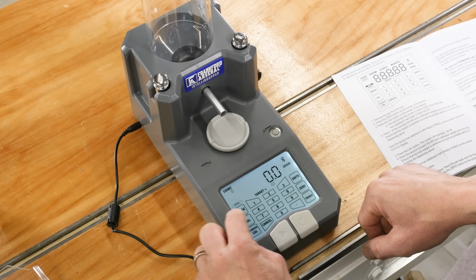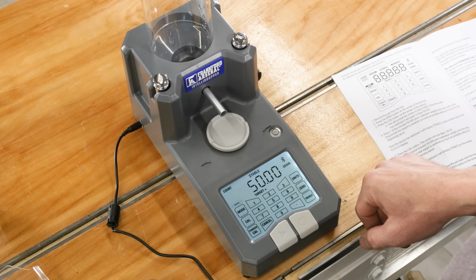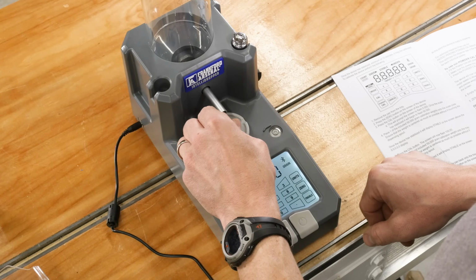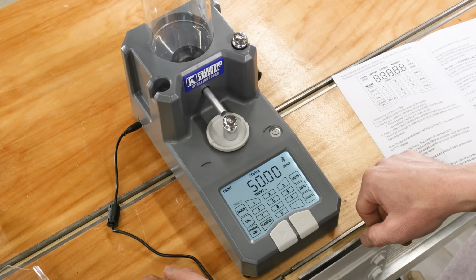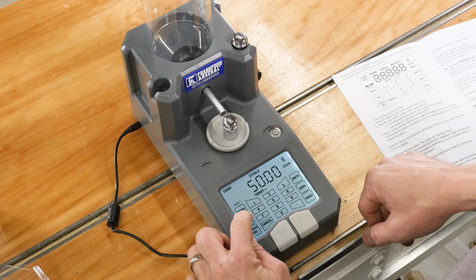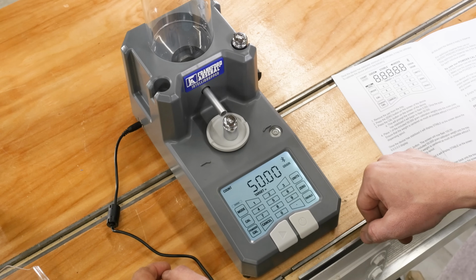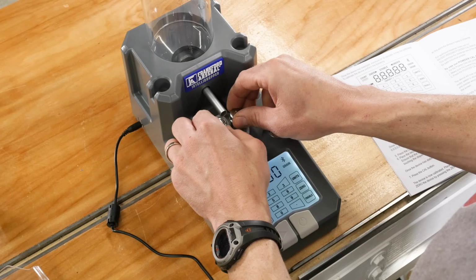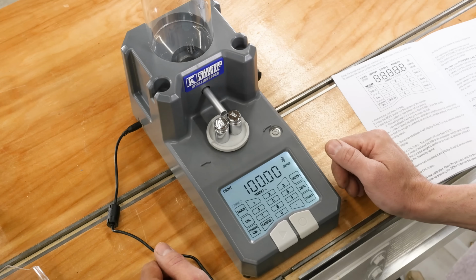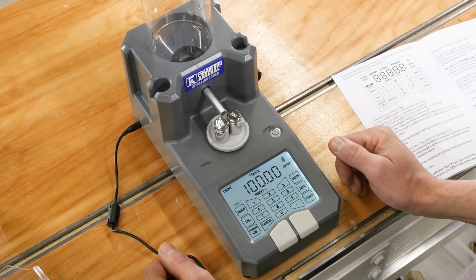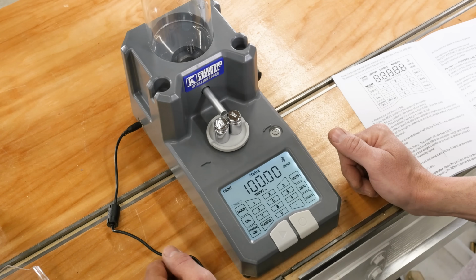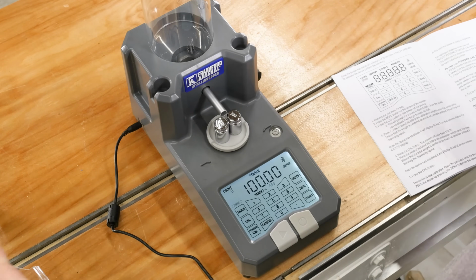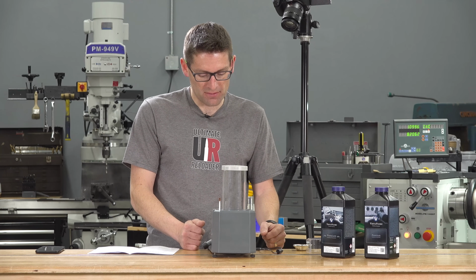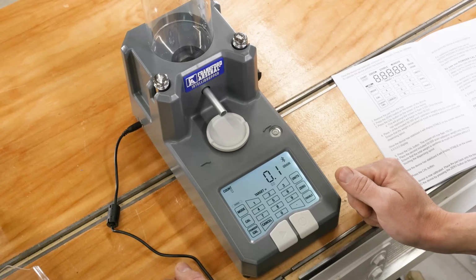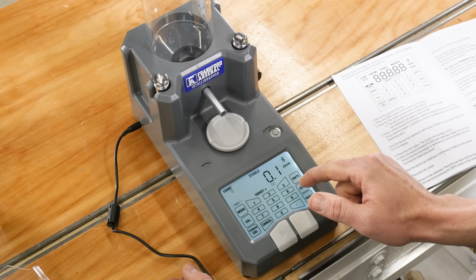Okay, now we're going to hit the cal button, and it's going to ask us to put the 50-gram weight on, and I'm going to center that. And then when that gets stable, we're going to hit the calibration button again. Now it should ask us for 100 grams. Okay, so we're going to put these side by side in the center without touching the discharge chute. Okay, so that's stable now. Hit calibration again. And there we go, pass. So that's all it takes to calibrate the unit. Okay, so we can take the weights off. We can go ahead and zero the unit out again.